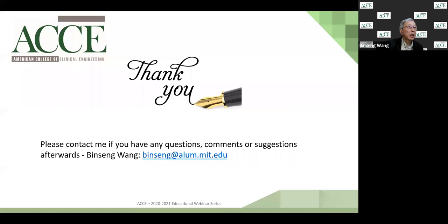Depends what you call calibration. Let me answer first about calibration. Calibration verification is indeed part of the safety and performance inspection. However, recalibration, if the device is found to be out of calibration, that should be considered a corrective maintenance. So you should close this work order for safety and performance inspection and say that the device did not pass the inspection, and I need to open a work order to recalibrate the equipment.